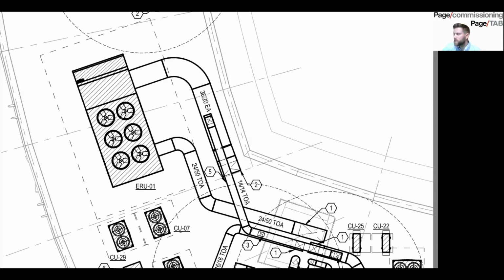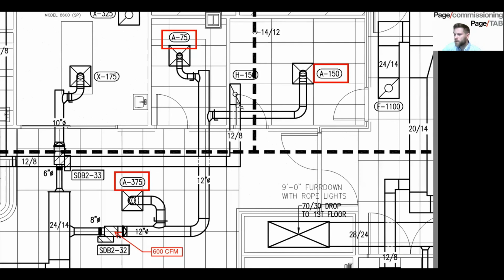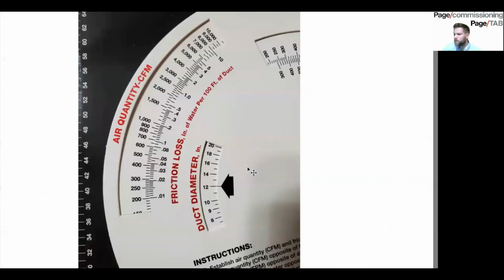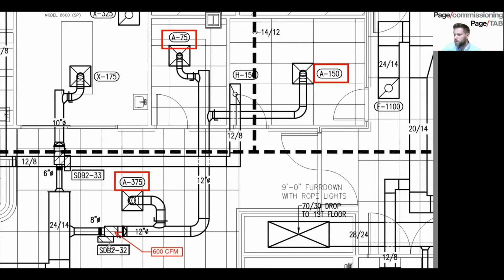Let's go through one more example. So for a round duct, if you have like this box, it's discharging to a 12-inch round. You're just going to add up all the CFM along this duct run, which is the 375, 75, and 150 equals 600 CFM. So let's see if that's sized correctly. So then we go to our ductilator. We're going to move until our duct diameter is at that 12, and we'll see the CFM that we can flow through it at 0.08, which is just over 600. So then this one would be sized correctly.